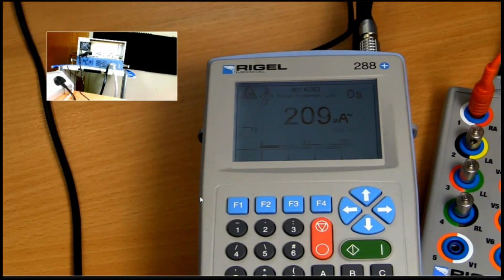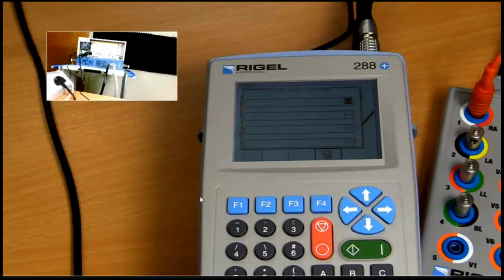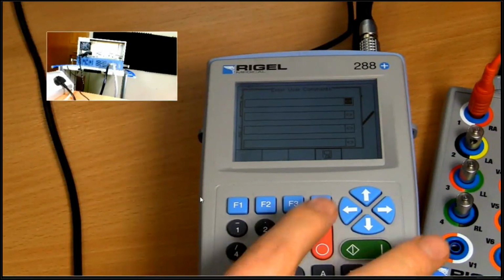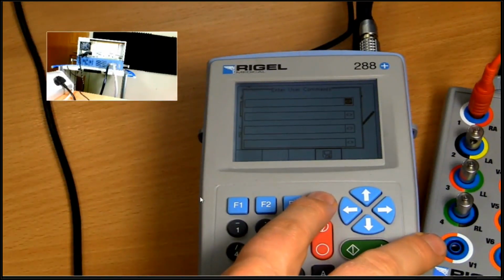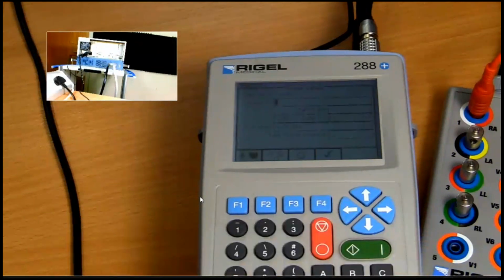Note that the fault conditions, or at least the live and neutral reverse, show on the screen at the end of the test. I'm quite happy with that. Now I'm going to save that test. And all of those test results are saved within the tester. I'm just going to turn that medical device off. It's really annoying. And that is the end of the demonstration. So it's something very quick.